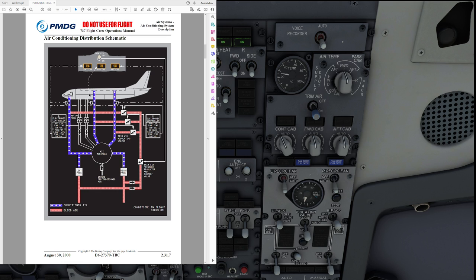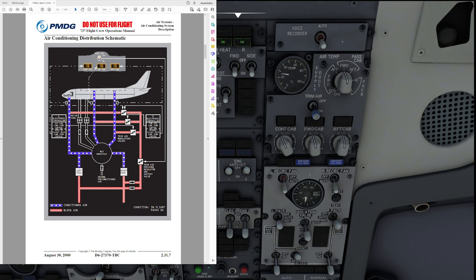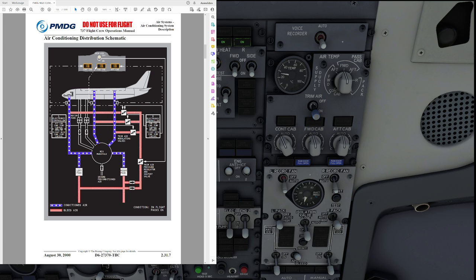Another difference here is that the 737-800 and 900 have two recirculation fans. We can see on the panel up here we have a left recirculation fan and a right recirculation fan. The recirculation fans are exactly as in the smaller 737s taking air from the cabin, feeding it back into the mix manifold to mix it with the fresh air and from there on it's going back into the cabin thereby reducing workload on the packs.